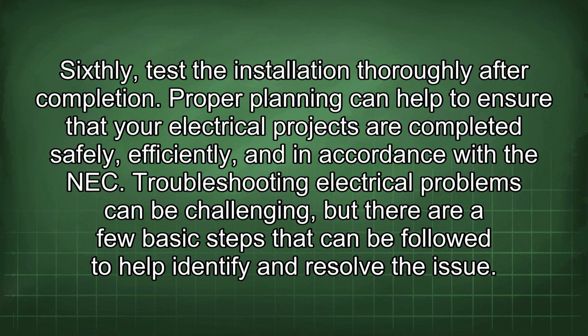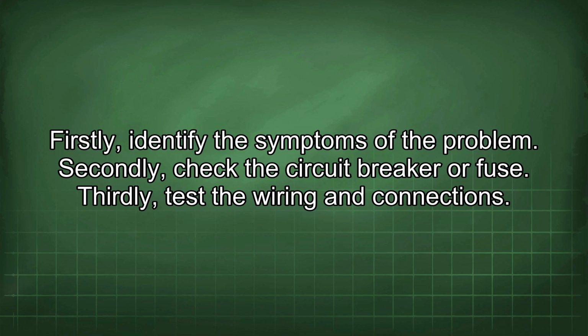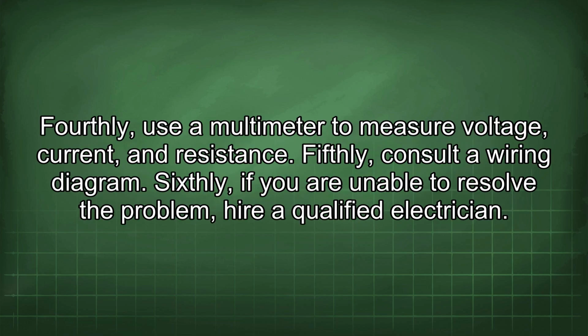Troubleshooting electrical problems can be challenging, but there are a few basic steps that can be followed to help identify and resolve the issue. Firstly, identify the symptoms of the problem. Secondly, check the circuit breaker or fuse. Thirdly, test the wiring and connections. Fourthly, use a multimeter to measure voltage, current, and resistance. Fifthly, consult a wiring diagram. Sixthly, if you are unable to resolve the problem, hire a qualified electrician.